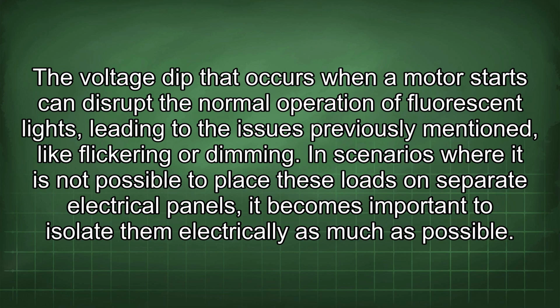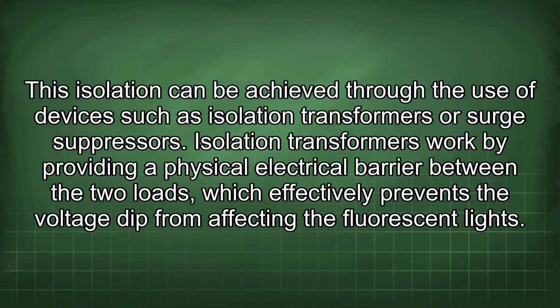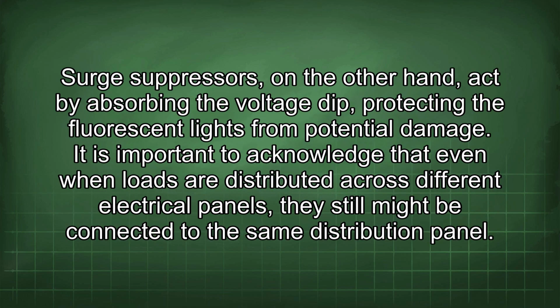In scenarios where it is not possible to place these loads on separate electrical panels, it becomes important to isolate them electrically as much as possible. This isolation can be achieved through the use of devices such as isolation transformers or surge suppressors. Isolation transformers work by providing a physical electrical barrier between the two loads, which effectively prevents the voltage dip from affecting the fluorescent lights.